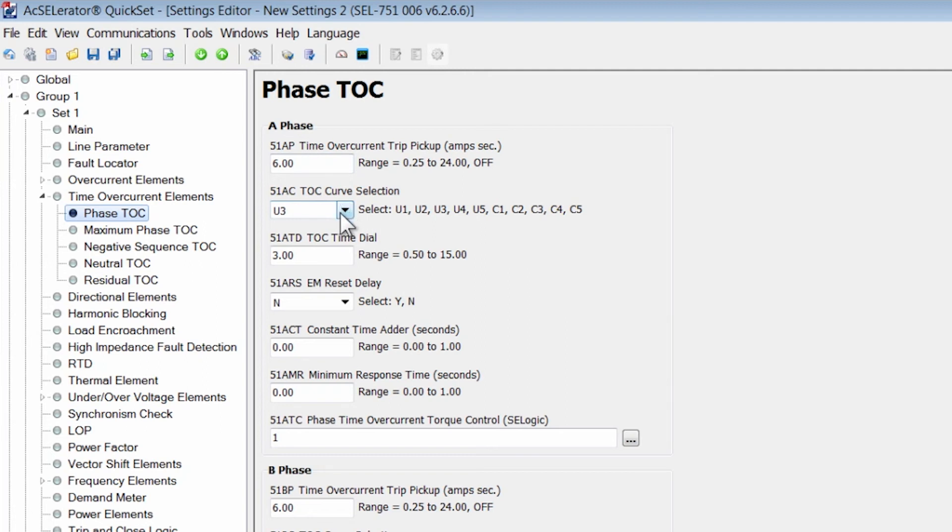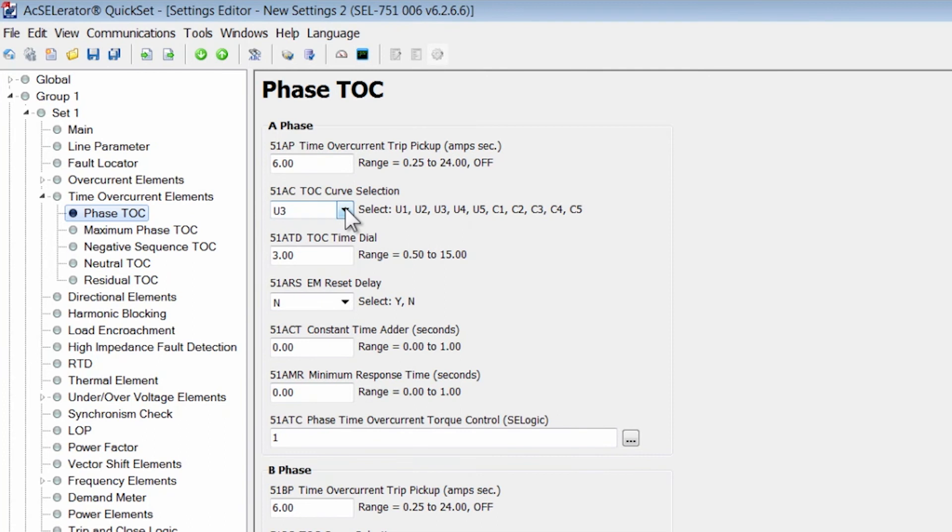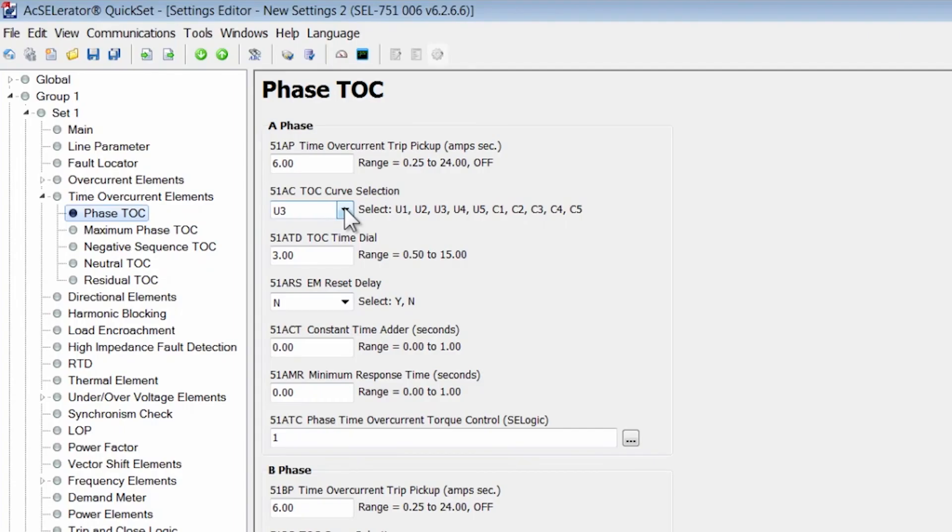These can be the IEC curves or the ANSI curves of U1, U2, U3, U4, and U5. If you're replacing or doing a retrofit application, you would want to select the curve that the electromechanical relay had previously. So let's assume the curve of the electromechanical relay was U3.